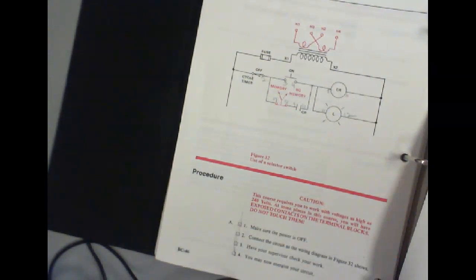So I didn't see cycle timer, thank you. I'll just mark that out. And then we'll use it normally closed. So basically it's going to act like a stop. We press this button, touch that button, it's going to bring in CR. It's going to sit, the light's going to come on, it's going to seal itself in until you do what? Until you hit the limit switch.